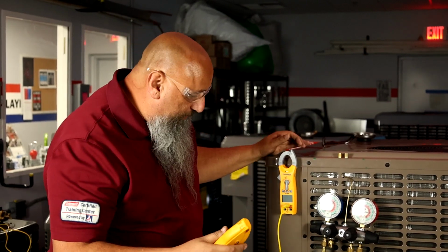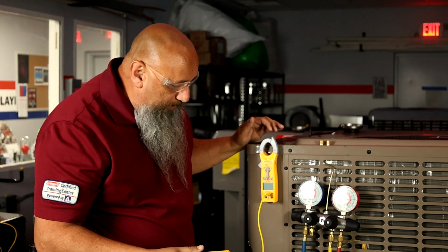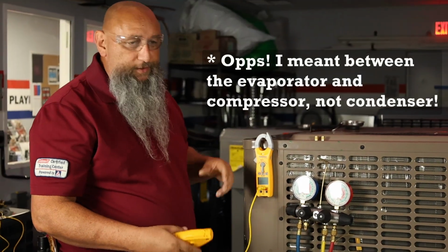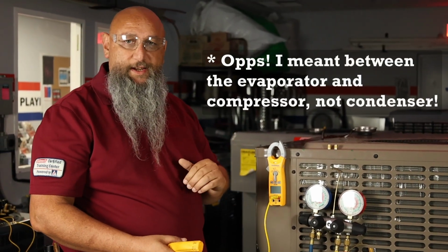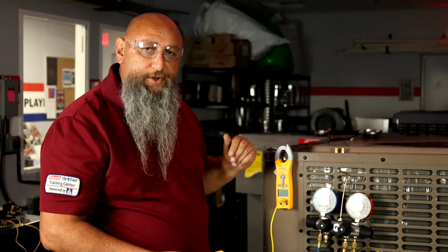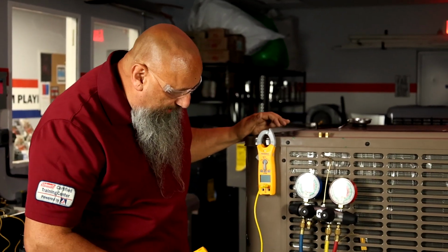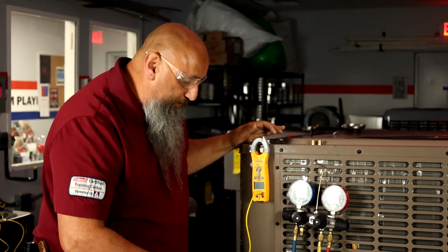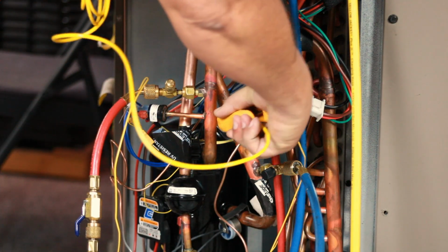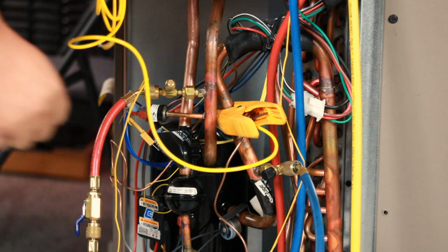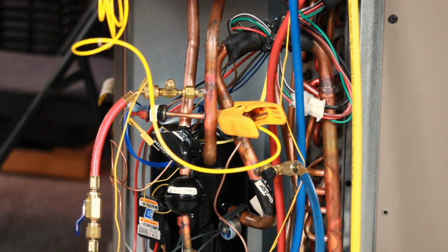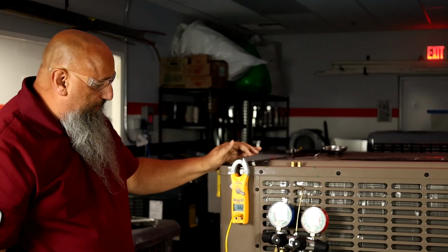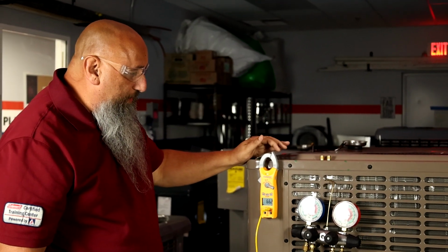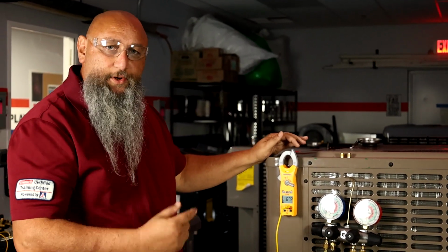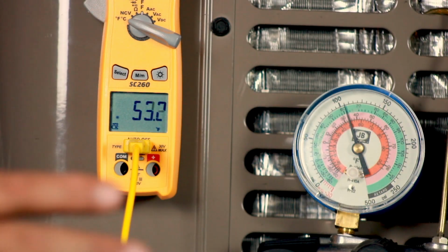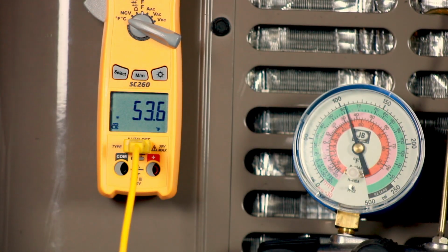And our proper connection today, since we're reading superheat, is going to be between our evaporator and our condenser. If this is a split system, you're going to probably take that at the condenser. This is obviously a package unit, so we're just going to clamp it in where it comes out of the evaporator, but before it goes into the compressor, just like this here. And then we're going to go ahead and set our meter to temperature and let it give us a temperature. And our next step is I'm going to start this unit up. So we've got everything connected. We're now getting our readings.